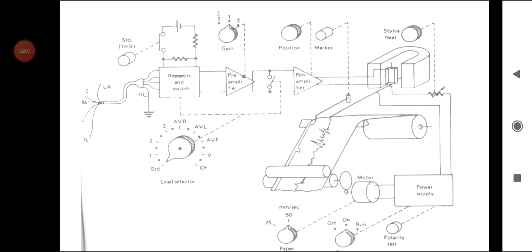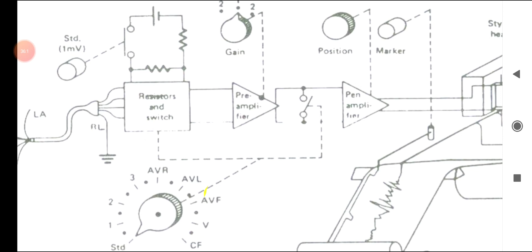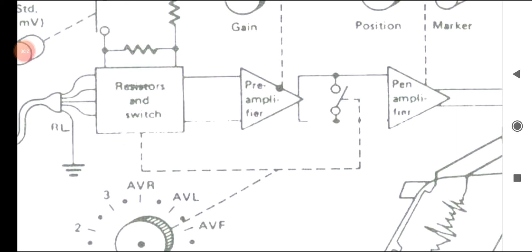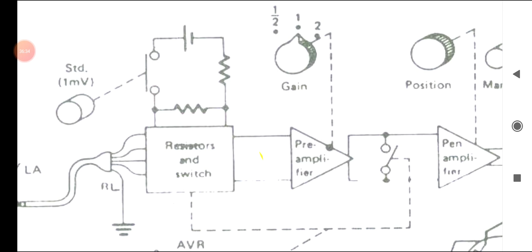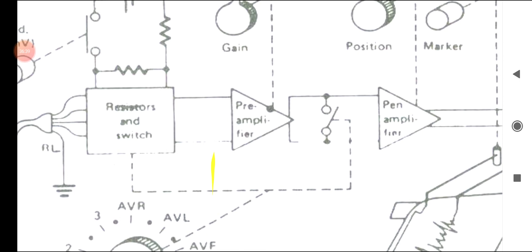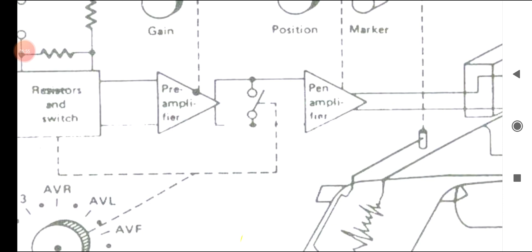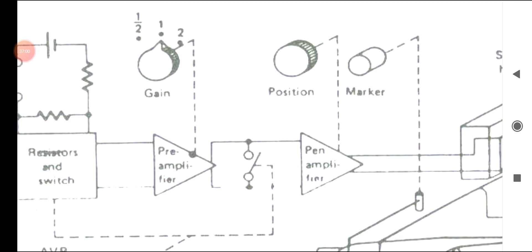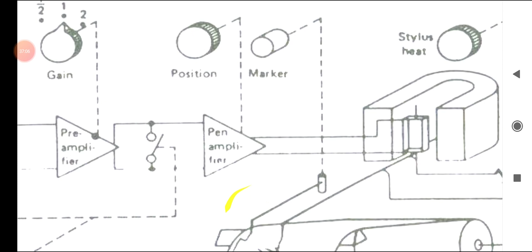The output unit consists of the lead connections given to resistors and switch, and standard 1 millivolt excitation. The lead selector switch has lead 1, lead 2, lead 3 and AVR, AVL, AVF and V and CF. It has a preamplifier with gain adjustment: half, gain 1, gain 2. Then it is connected to the pen amplifier.